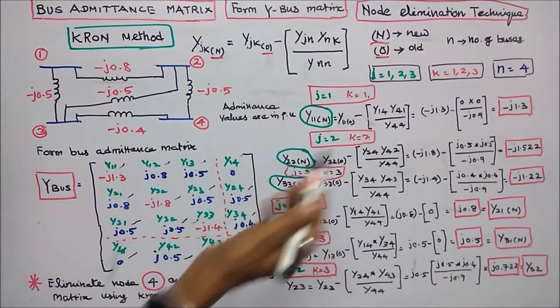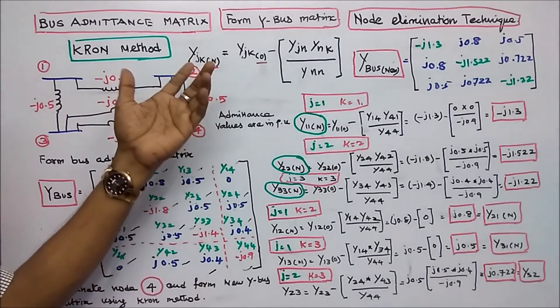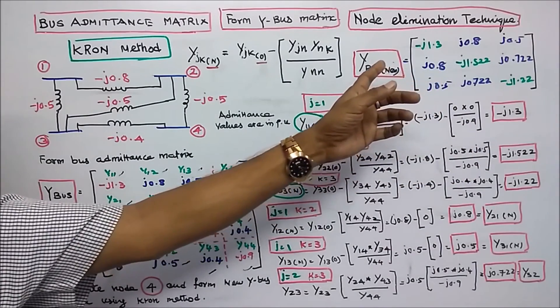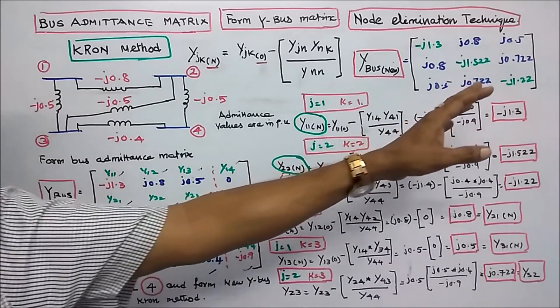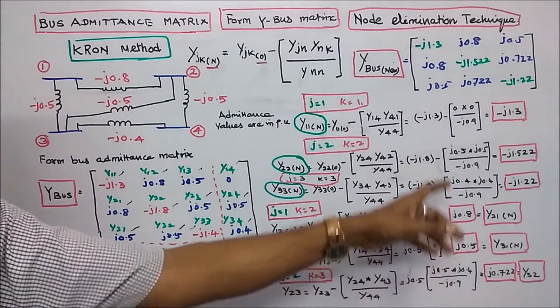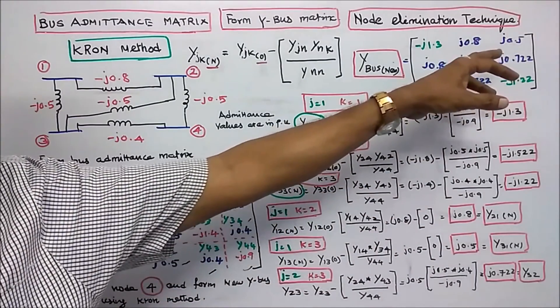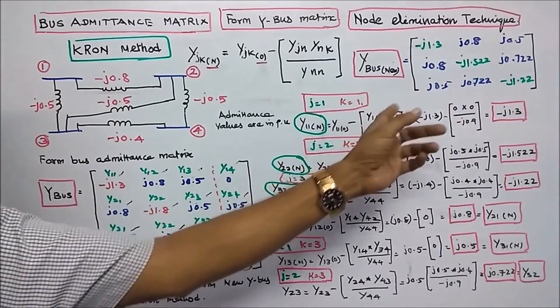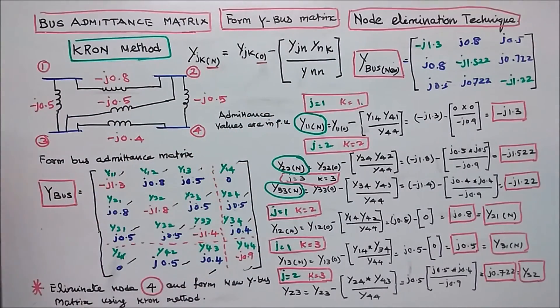Next we form the new bus admittance matrix. By using Kron's reduction method to eliminate node 4, we get a 3×3 matrix with: Y11 = minus j1.3, Y22 = minus j1.522, Y33 = minus j1.22. The off-diagonal elements are: Y12 = Y21 = plus j0.8, Y13 = Y31 = plus j0.5, Y23 = Y32 = plus j0.722. This is the new bus admittance matrix after eliminating node 4. With this I conclude my lecture, thanks for listening.